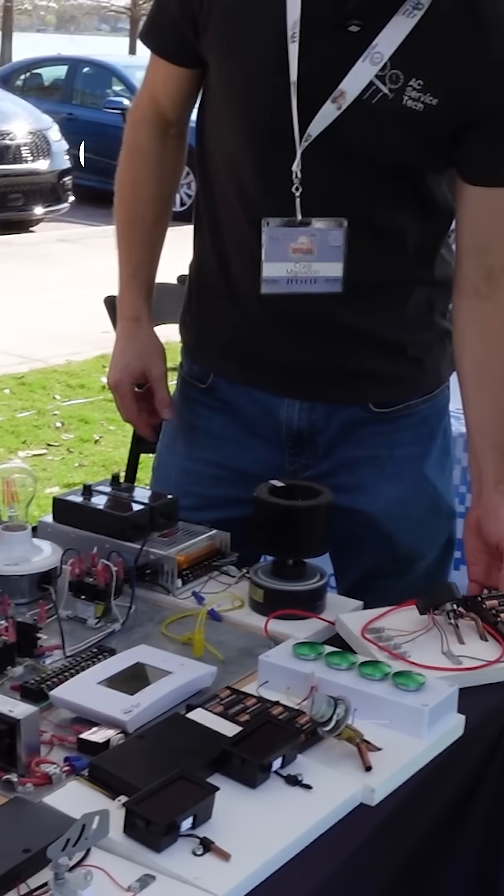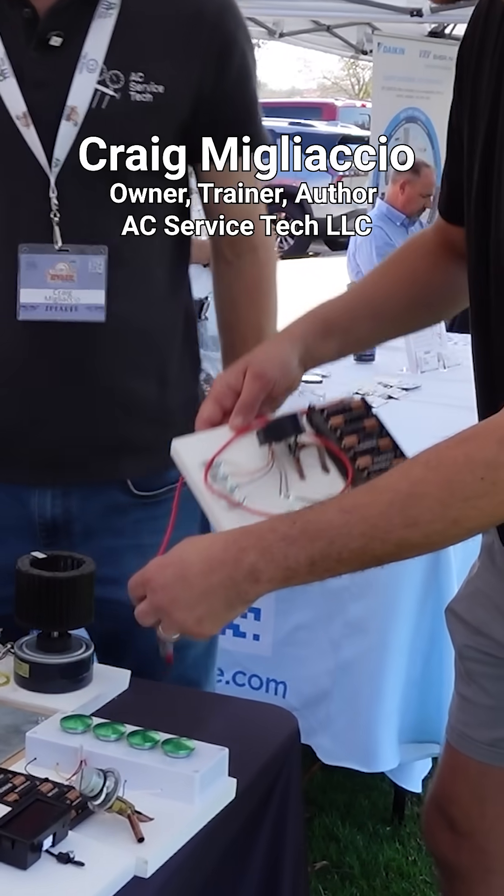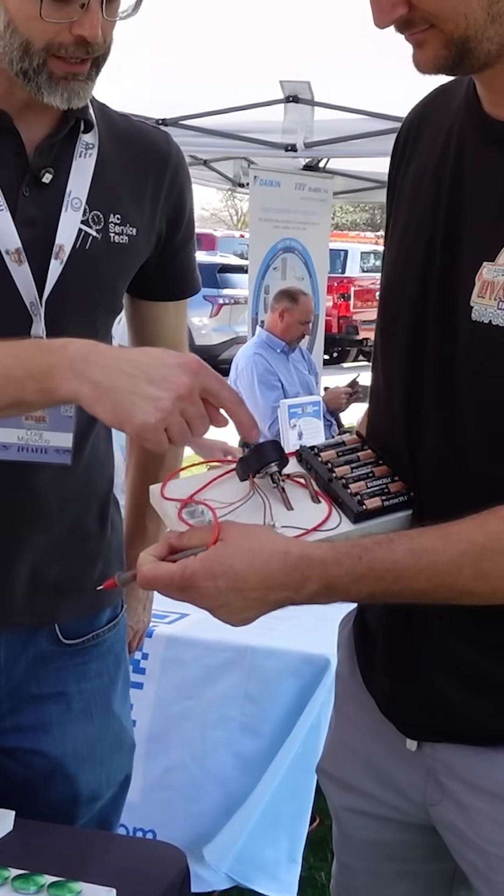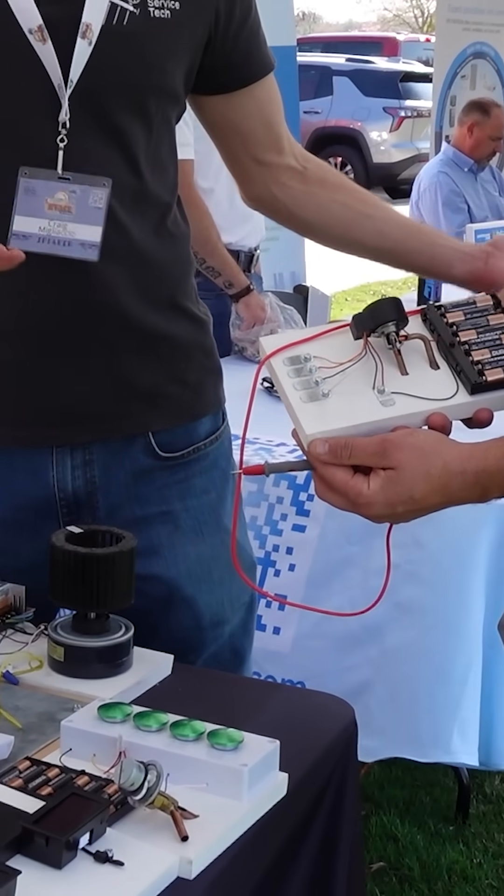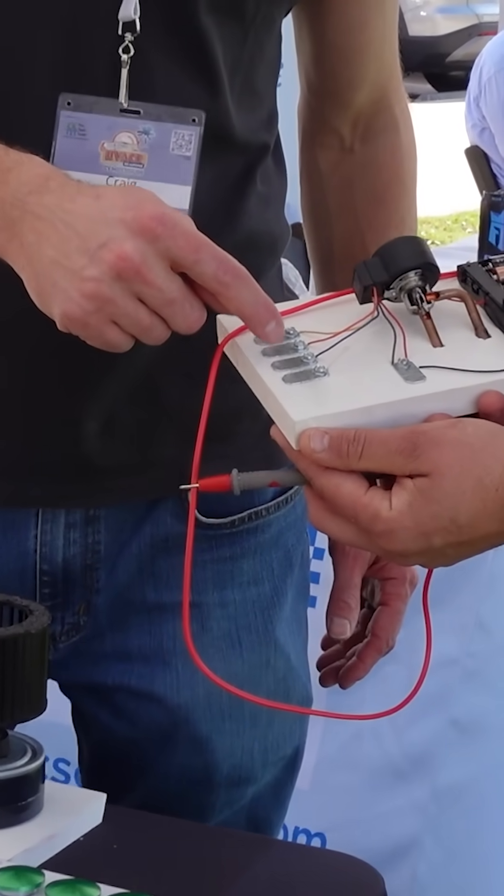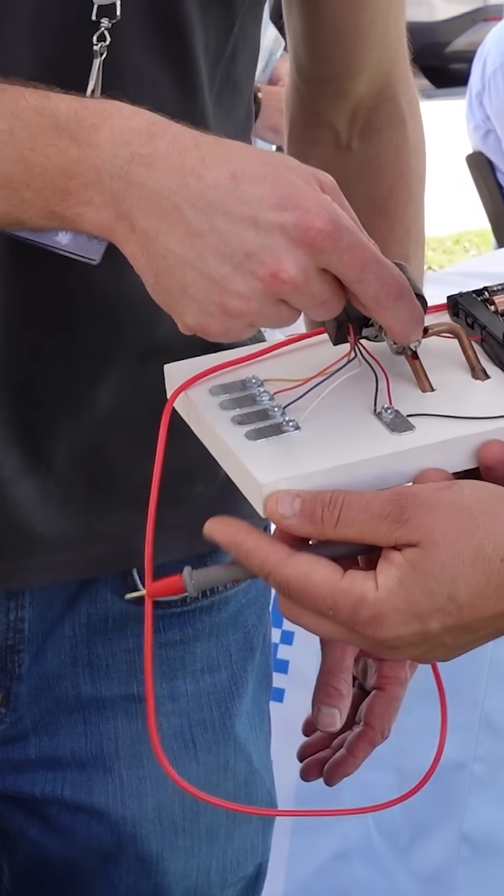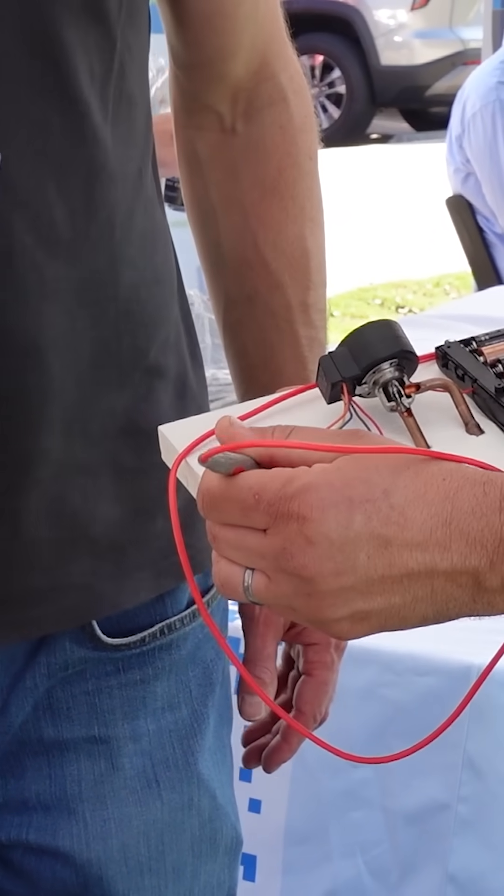This one is showing technicians the different steps of an EEV. So this EEV has like 250 steps and each one of these is a 12 volt pulse. It's going to open or close this little pin position.